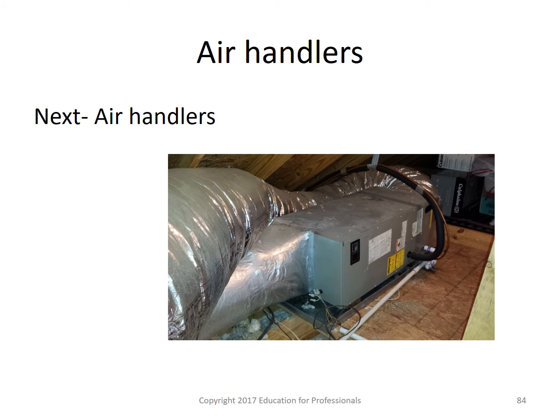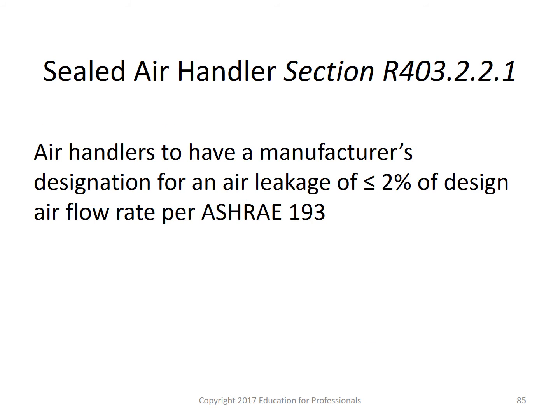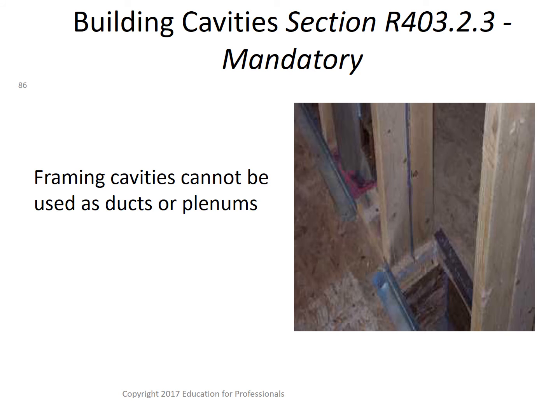Next, we'll take a look at what is required for air handlers. And here are some of the requirements on the air handler. Basically, air handlers must have a manufacturer's designation for air leakage of 2% or less of design airflow. And we'll take a look at why building cavities cannot be used for ducts or plenums, for much of the same reasons that we talked about with duct air leakage. It causes the same problems, with different airs and gases being drawn into the interior environment.